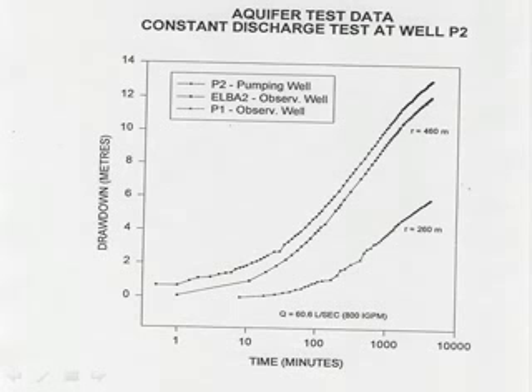After 6 months, that's what our heat plumes would look like under the campus. But that's assuming that our aquifer is fairly uniform in terms of flow throughout that whole aquifer. And when you look at it, we say that the aquifer thickness is 60 meters. Well, if we're dealing with fractures and the flow is preferentially within the fractures, it's not through the whole 60 meters, it's going to be something less than that. So what happens to our heat plumes if instead of 60 meters, we use 6 meters as our aquifer thickness?